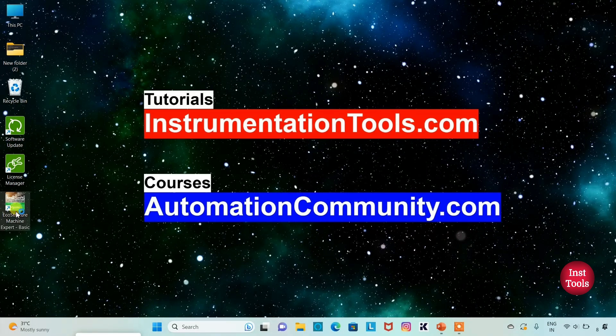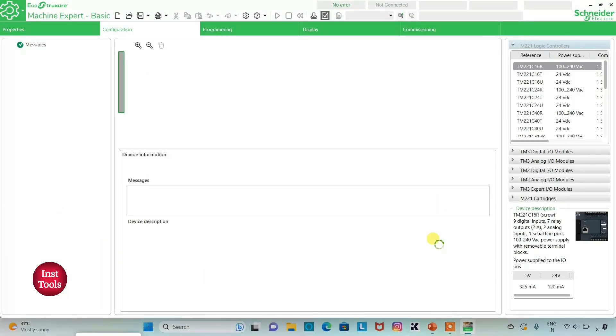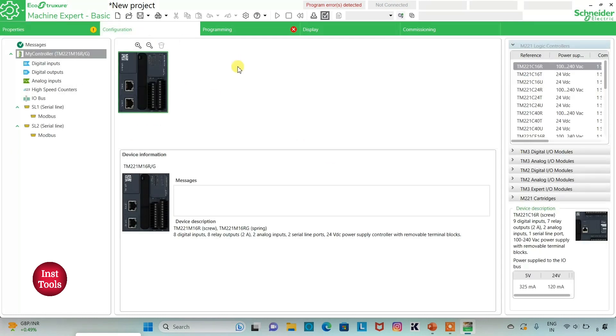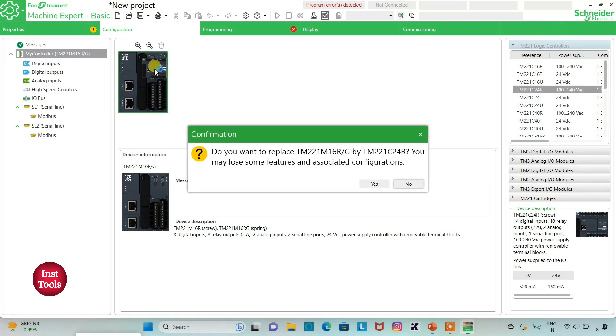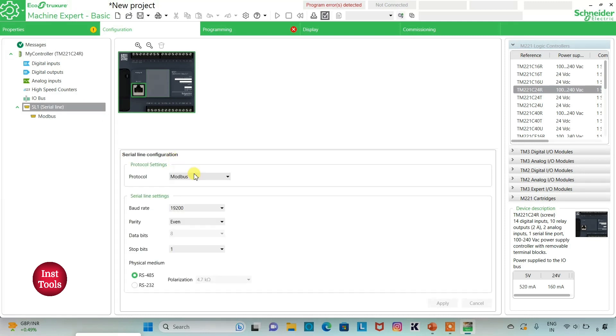I will open EcoStruxure Machine Expert Basic. Firstly, let's keep read protection as active and write protection as active, and then click on apply. Then I will go to the configuration tab where I can select a device. Here is a list of different logic controllers. I will select TM221C24R. I can click on it and drag it here. It asks 'Do you want to replace? You may lose some features and associated configurations,' so I will click on yes. Then I can also go to the serial line where I will select protocol as Modbus and then click on apply.